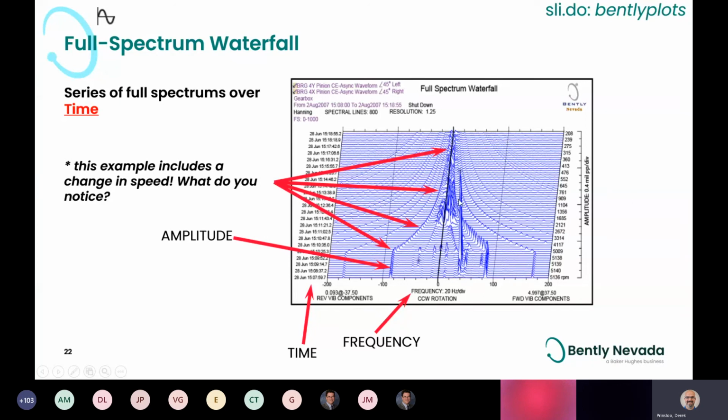And if we look, we only see it in the forward direction, but not in the reverse direction. If I were in a classroom environment, I could ask folks, what shape of orbit would you expect to see there? But I'll answer it for you: if it's all forward and almost no reverse, this would be a very circular orbit. So it seems like something went big down here. But then as you go farther down, as the forward and reverse are more similar, you'll likely see a more squashed orbit at these lower speeds.